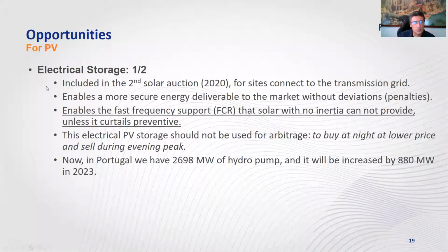Regarding opportunities, the good news is that we have electrical storage. This was included already in the second solar auction in 2020, only for the transmission grid, and this enables the promoter to go to the market with more secure power delivery, minimizing deviation and penalties in the market. The electrical storage will also allow fast frequency support, since solar doesn't have inertia and cannot provide synthetic inertia, so you can use storage to back up PV. This is a very good combination.